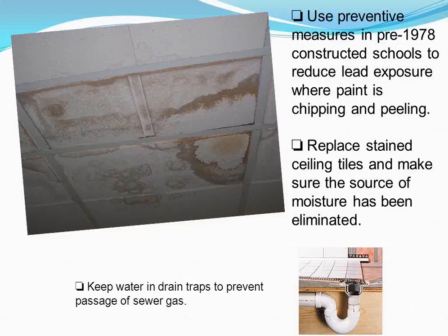That's correct. Again, I'm going to sound like a broken record: don't forget. Just like our custodial staff is asked to every Friday night, whatever area there is, make sure that they have a sink, they run a little water that Friday night so the trap doesn't dry up. Floor drains, put some water down the floor drain every Friday night. Just do it. It's on your schedule. You've got to do that still. It still has to be maintained.